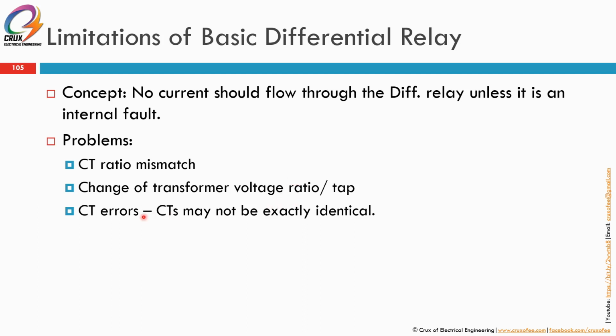Third is CT error. CT may not be exactly identical. Even if you buy three CTs for the red, yellow and blue phases with the same CT ratio, 1000/1, 1000/1, there will still be some error, because everything is man-made. There is some limitation there, such as copper thickness. So this one may measure slightly more and that one slightly less, but still within tolerance. But because the differential relay is very sensitive, the setting is very low, so this CT error may contribute to mal-operation of your differential relay.